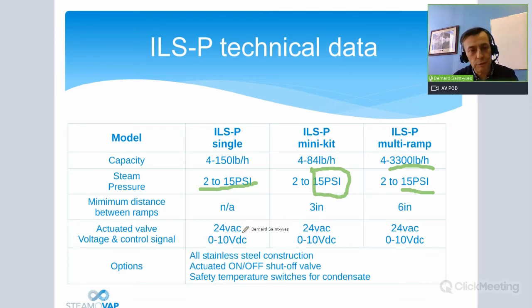The actuated valve is 24 volt AC, with 0 to 10 or 2 to 10 volts for the control signal. The options are all stainless steel construction. Sometimes the unfired steam generator is made of stainless steel, and all the steam pipe and the whole system will be designed by the engineer all in stainless. So we have an option to have all stainless steel construction. The valve body, the trim, of course the strainer will be stainless steel, and even the steam trap can be stainless steel.